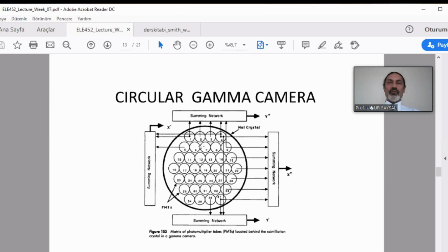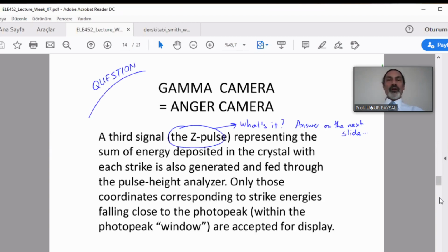Usually a couple of centimeters is the diameter of each photomultiplier tube, and the resolution of the nuclear imaging camera, or gamma camera, also called the Anger camera, the resolution of the positioning of a nuclear imaging experiment is up to 5 to 10 millimeters or so, okay? So these can be calculated from the multiple gamma ray receptions by the photomultiplier tubes and processing with computer methods.